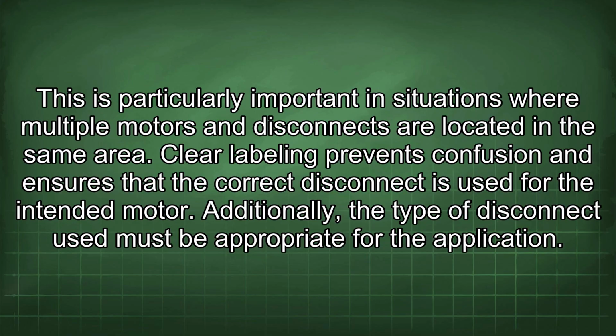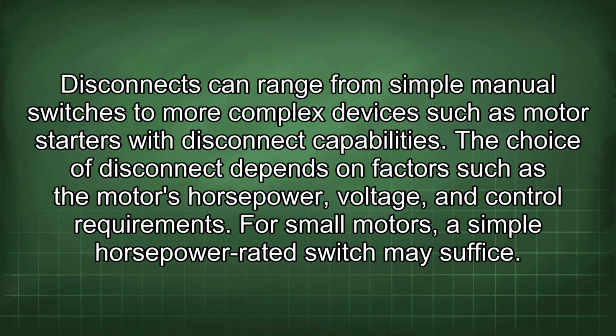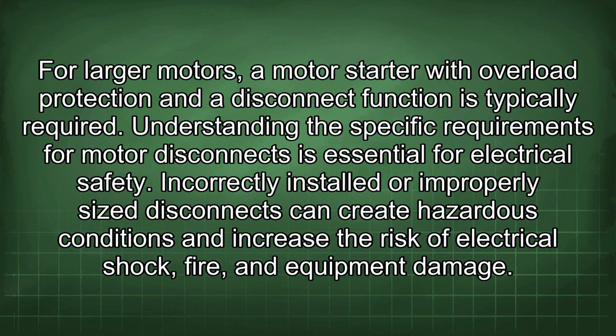Additionally, the type of disconnect used must be appropriate for the application. Disconnects can range from simple manual switches to more complex devices such as motor starters with disconnect capabilities. The choice of disconnect depends on factors such as the motor's horsepower, voltage, and control requirements. For small motors, a simple horsepower-rated switch may suffice. For larger motors, a motor starter with overload protection and a disconnect function is typically required.